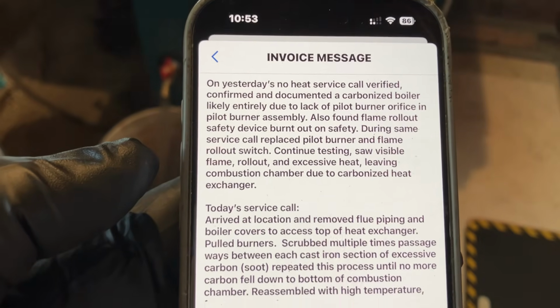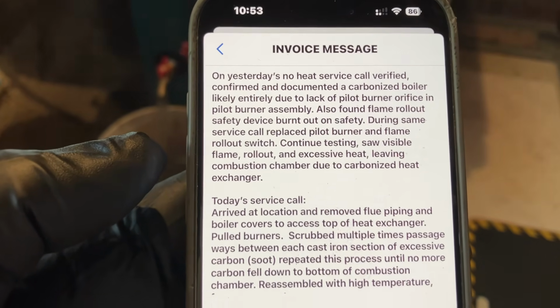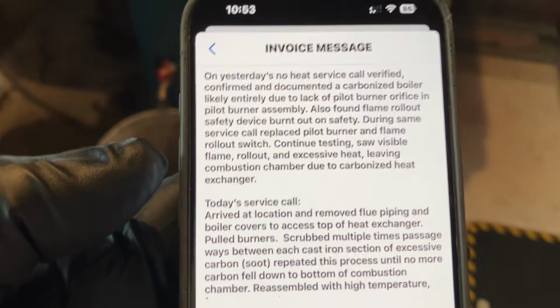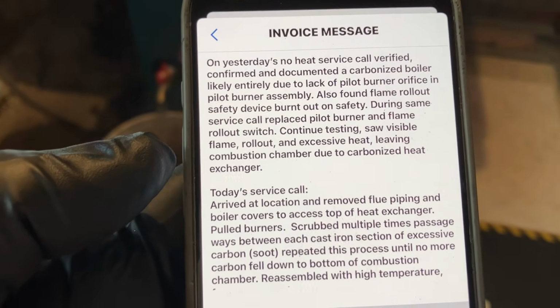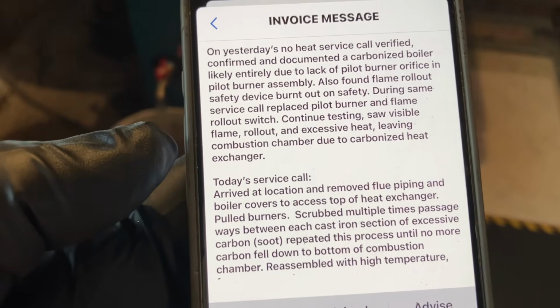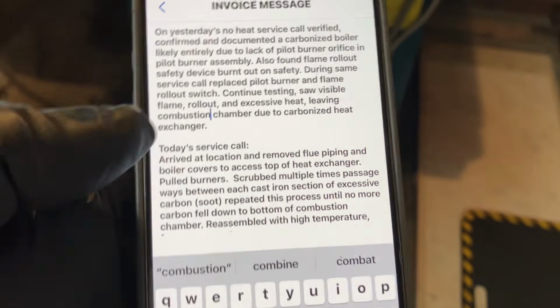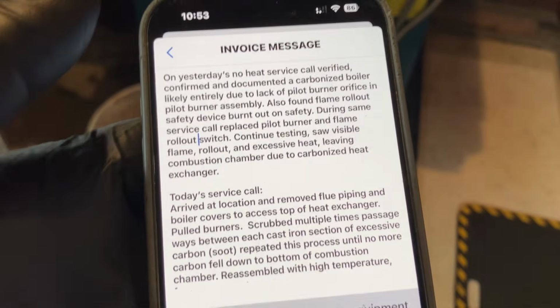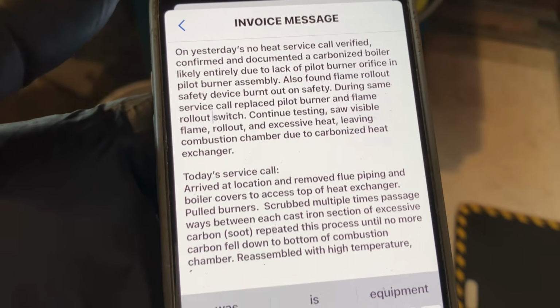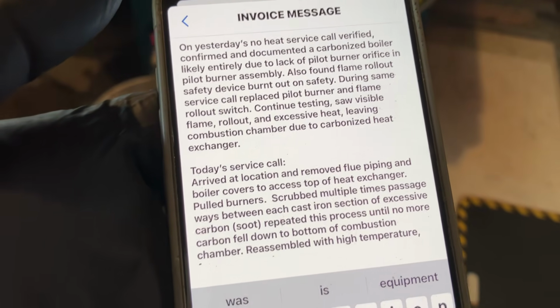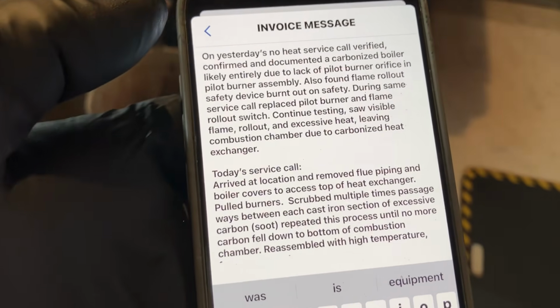Also found the flame rollout safety device burnt out. During the same service call, replaced the pilot burner and flame rollout switch. Continued testing, saw visible flame rollout and excessive heat leaving the combustion chamber due to a carbonized heat exchanger. Yeah, the commas aren't where they should be.